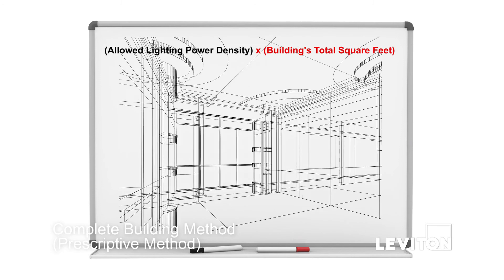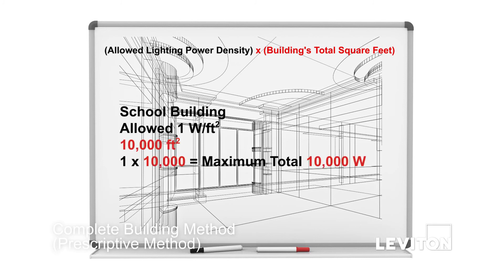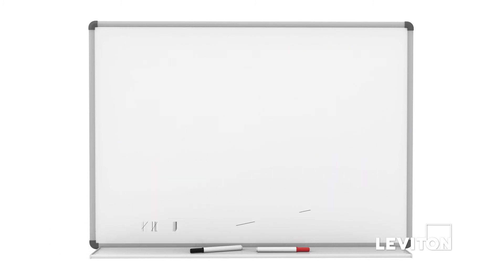If the design is a school building, you are allowed one watt per square foot. So if you have a 10,000 square foot building, you are allowed a maximum total of 10,000 watts of lighting across the entire building.